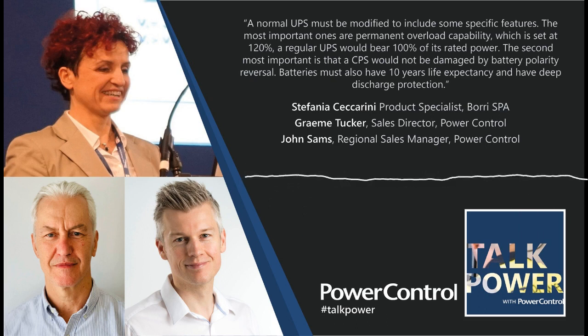Yeah, so we'll be talking about here UPS systems working as central power supply systems to comply with EN50171. So this is life safety systems for emergency battery backup systems. So this really is a UPS product that is being used in the traditional central battery system market, which has become a lot more prevalent in the last couple of years, mainly because the technological advancement of UPS systems has enabled them to run as a more efficient, more cost-effective system over a traditional central battery system that's perhaps comprised of an inverter and a separate rectifier assembly.